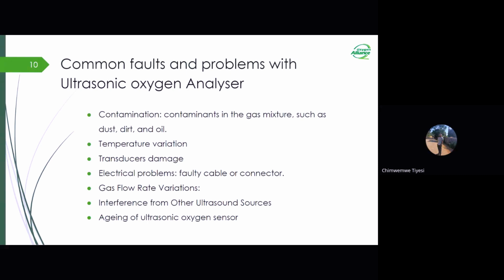One other thing that affects the accuracy of the reading is sensor aging. Although ultrasonic oxygen sensors and analyzers can last up to 5 years without need for recalibration, the sensor can age over time and usage. So the sensor performance will degrade, leading to inaccurate readings.